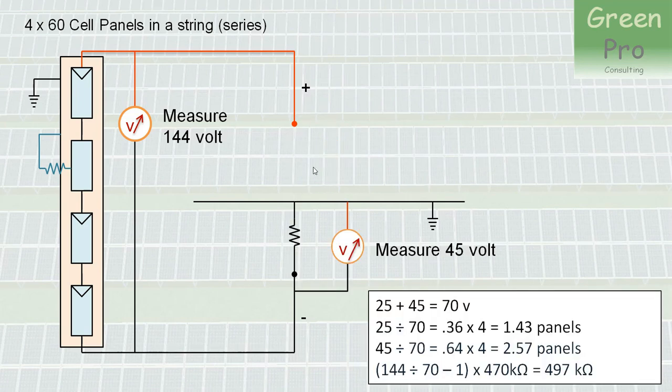Now, how do you interpret these voltages? First of all, you say 25 plus 45 is 70. 70 is a significant proportion of 144 and therefore I have a problem. Secondly, you say 25 divided by 70. Now, remember the 25 you measured on the positive side is 0.36 times 4 panels, because you have 4 panels in series there. And that is 1.43 panels. So you measured it on the positive side. So you start there and you say 1.5, and that's where my problem is in this panel. On the other side, you can say I measured 45 volts. So 45 divided by 70 is 0.64 times the 4 panels is 2.57. So you count 1, 2 and a half, and lo and behold, you end up at the same point. And that makes sense.